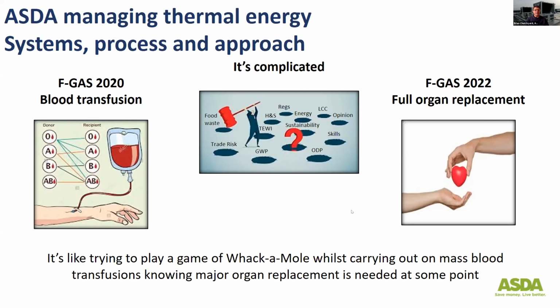Within the F-gas regulation, we've been extensively replacing refrigerant gases in existing systems. The analogy would be a blood transfusion. So taking out the high GWP refrigerants and putting low GWP refrigerants back into those systems has actually driven a return on investment for us, because we do get greater energy efficiencies by doing that replacement. But inevitably, we know that we're going to have to do an organ transplant within our estate, which is fundamental replacement of all systems in our estate. So what do we replace those systems with?